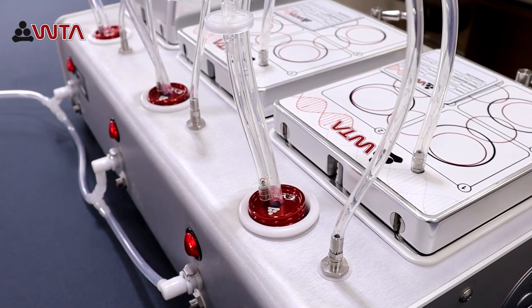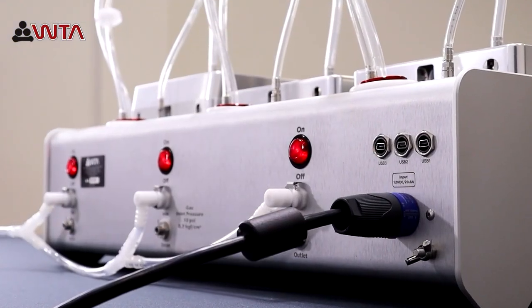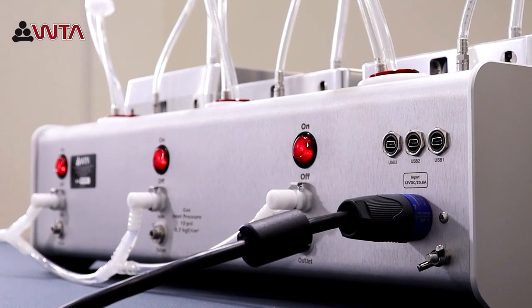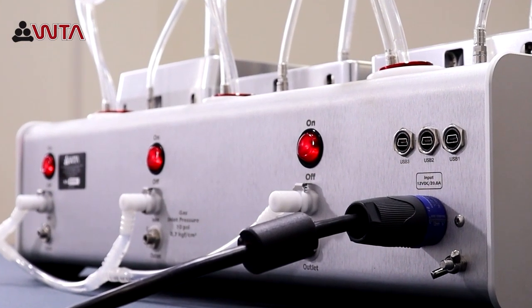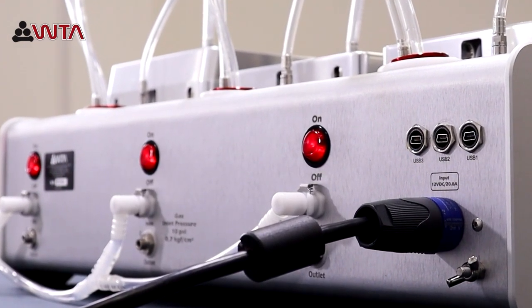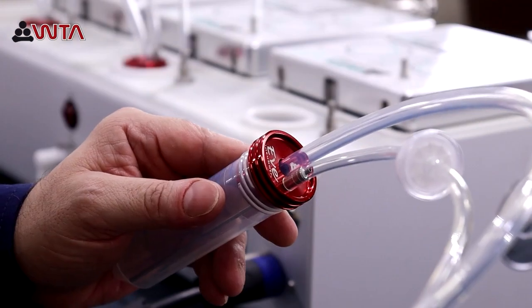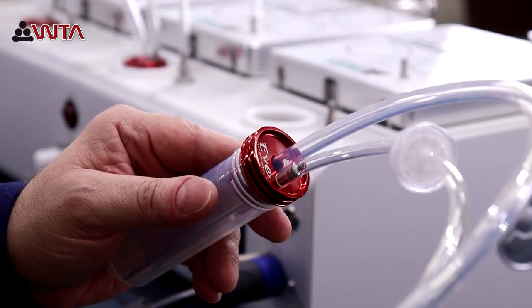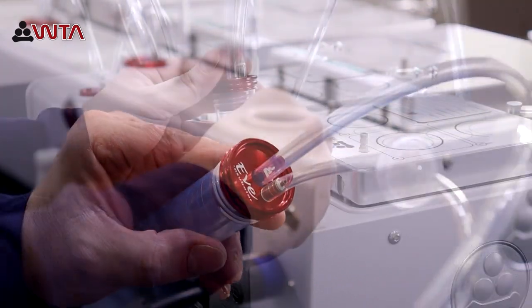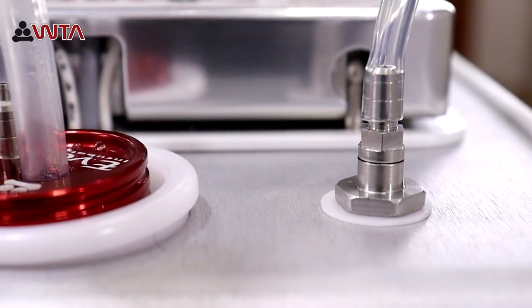Let's move on now to installing the incubator. To begin with, we will set up the gas preheating system. Connect the thinnest hose, the one with the filter, to the red aluminum stopper tube lid. Then, fit the other side of the hose into the connector located at the base of the incubator.